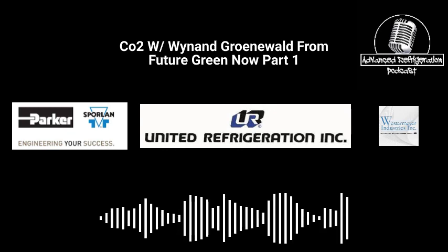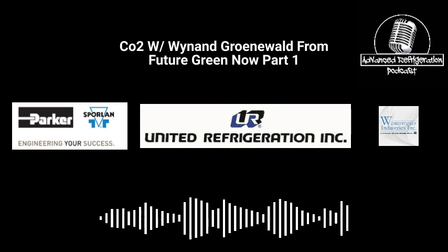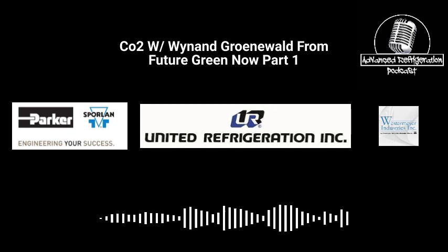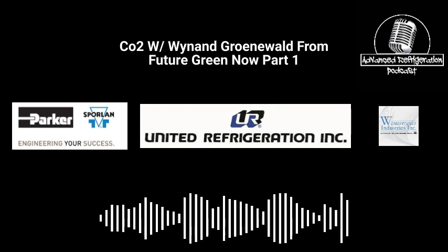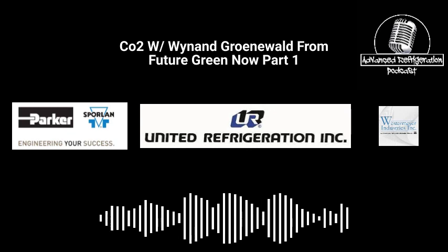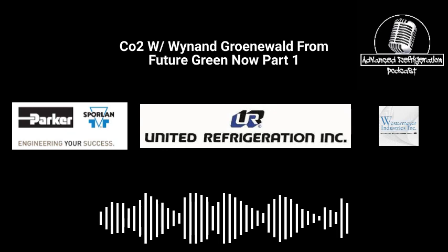See, the whole thing with that is we're so cold outside with ambient, and say we got a 4-fan gas cooler. And of course, all these manufacturers are staging all the fans at the same time, which I wholeheartedly disagree with. So they start out, say the minimum speed's 10%. So those EC fans come on at 10%. You have 4 fans moving. You basically have an entire fan running almost 100%, but between the 4 of them, it's just so much air volume that at that temperature, it just instantly shoots down before the controller could even react to the PID change. That's where the bypass would come in, right?